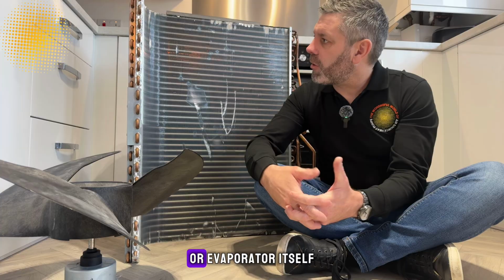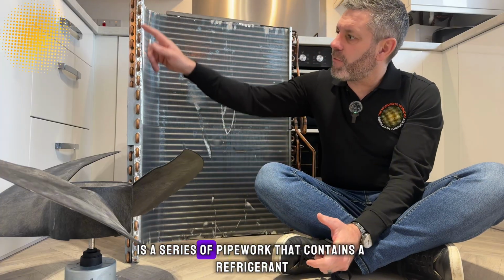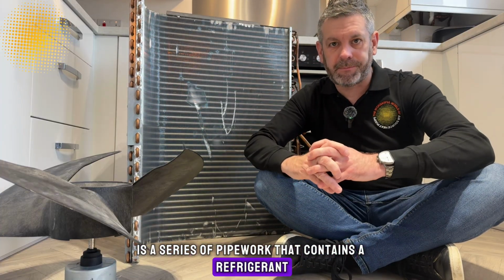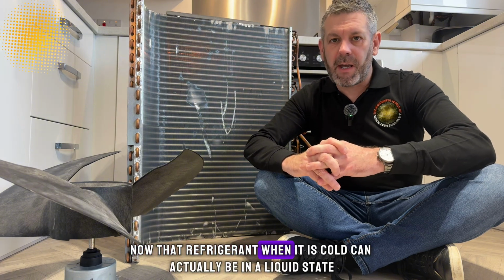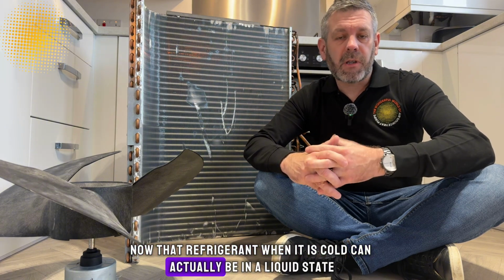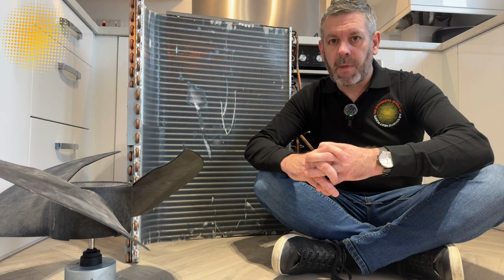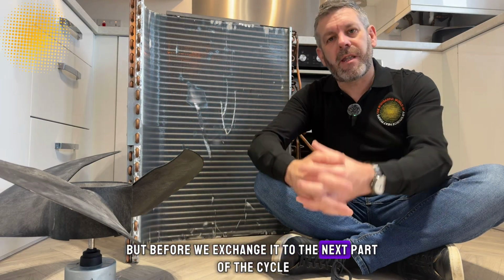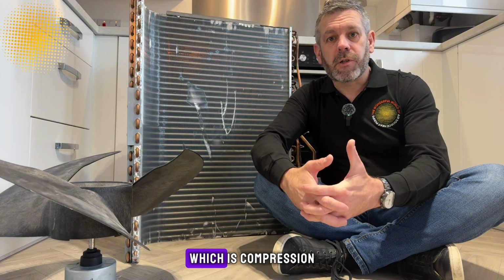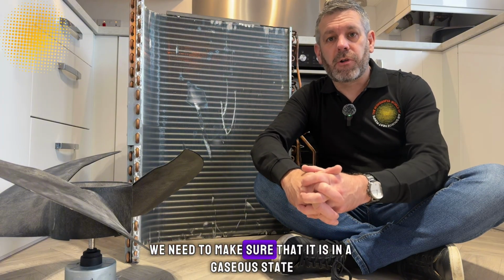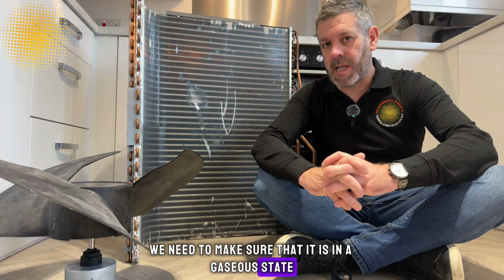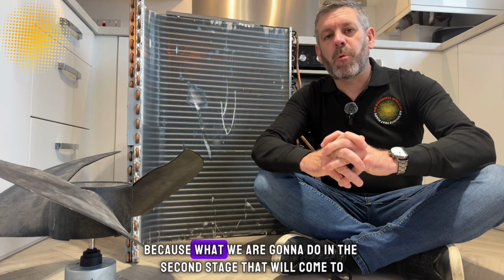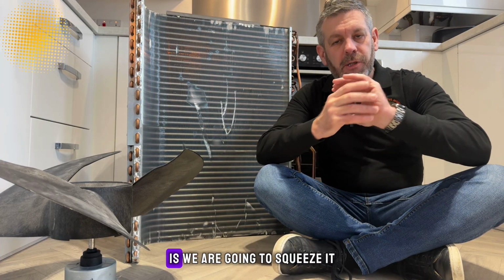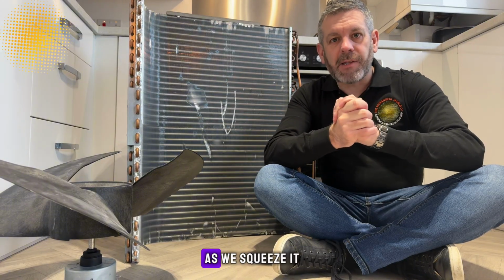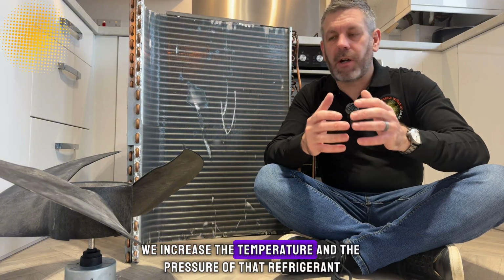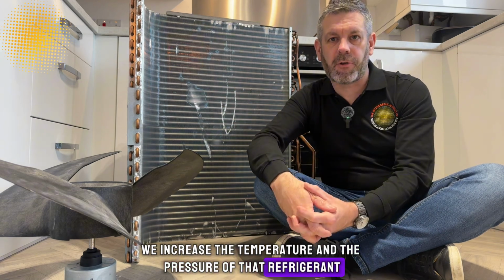Now, the heat exchanger or evaporator itself is a series of pipework that contains a refrigerant. That refrigerant, when it is cold, can actually be in a liquid state. But before we exchange it to the next part of the cycle, which is compression, we need to make sure that it is in a gaseous state, that it is a vapor. Because what we are going to do in the second stage is squeeze it. As we squeeze it, we increase the temperature and the pressure of that refrigerant.